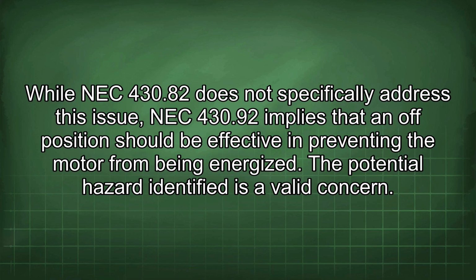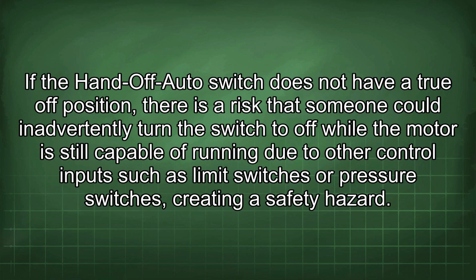The potential hazard identified is a valid concern. If the hand-off auto switch does not have a true off position, there is a risk that someone could inadvertently turn the switch to off while the motor is still capable of running due to other control inputs such as limit switches or pressure switches, creating a safety hazard.